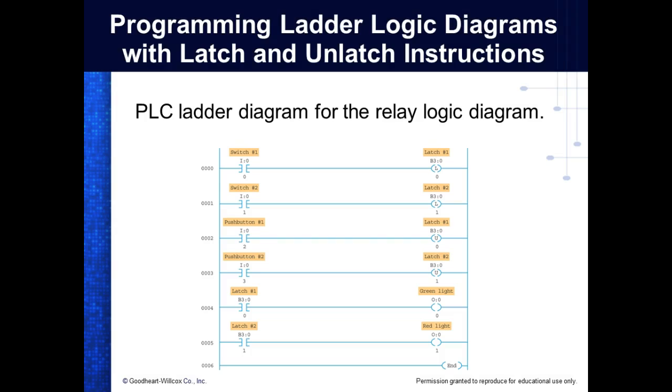This instruction, so this is pretty good. This is okay. This is done with our LogixPro. In LogixPro, your symbols use orange. In RSLogix, they'll use green, right? 90%. But notice what he's using. He's using B3. He's not using an output port. He's using B3. So if you use the B3 register, it does not use one of your output ports. Y'all understand that? And these are relay contacts that never leave your control diagram.